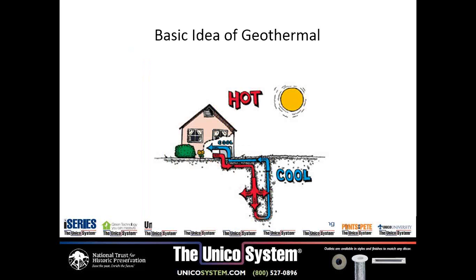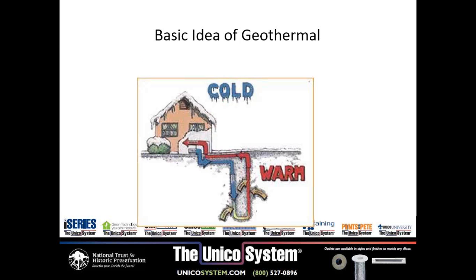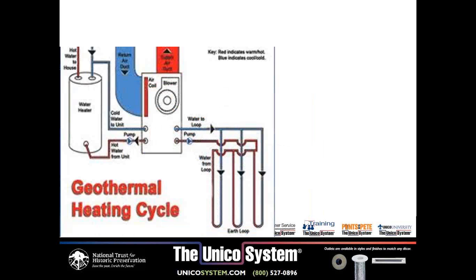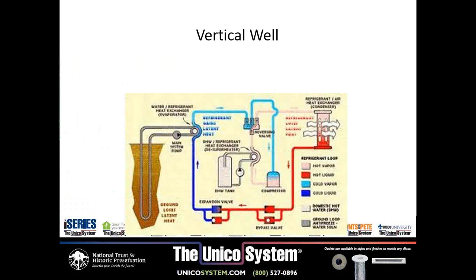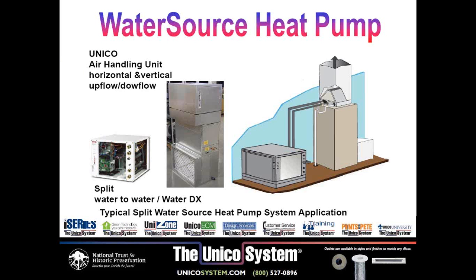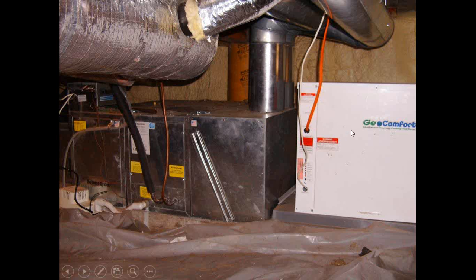This is a very common concept, especially in some of our rural markets in the United States: geothermal. What they're doing is they're drilling a well. You have the same temperature year-round when you get below a certain level. For instance, anyone who's been in a cave knows that they stay at a pretty even 50 degrees year-round. So a geothermal system works as both heating and cooling. And this is not an item we make, but there are many companies out there who do make geothermal equipment. As for the Unico system, here you see one with a vertical well. As far as the Unico system is concerned, we are merely using it, as you can see in this example right here. Here's the geothermal system. Off to your left is the Unico system.